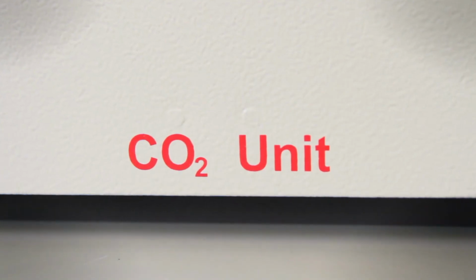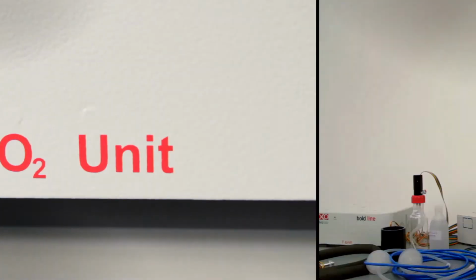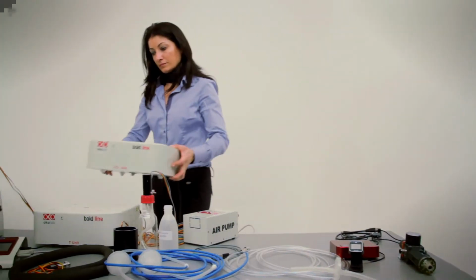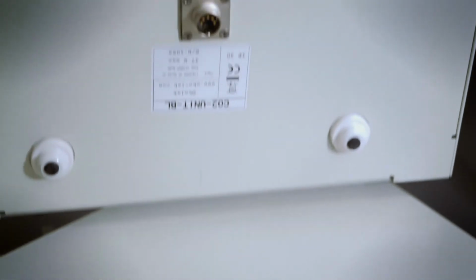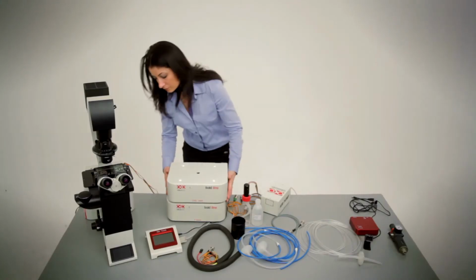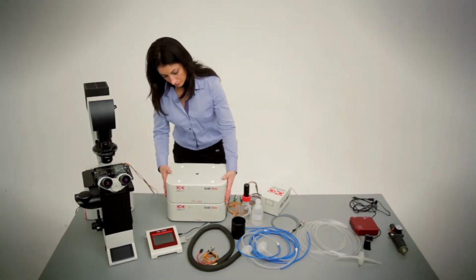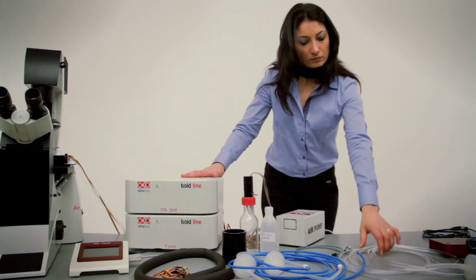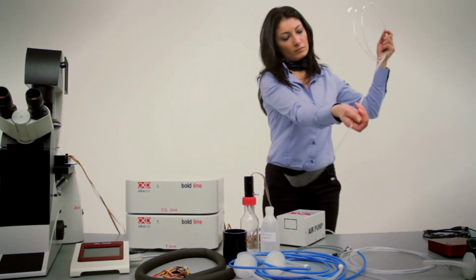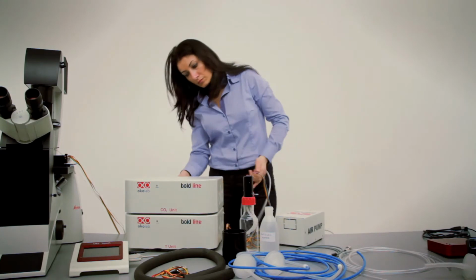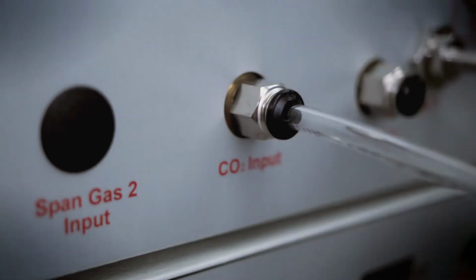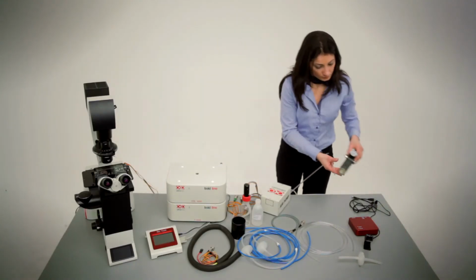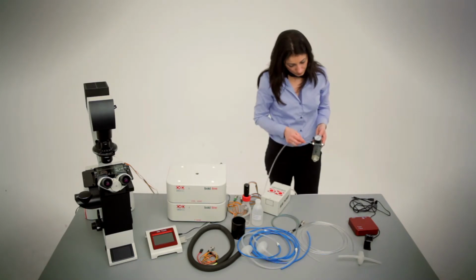Step 2. CO2 unit. Connect the gas controller to the temperature controller through the cableless connector. The positioning order of the controllers is not relevant. Connect one of the two transparent silicon tubes to the CO2 input push-in connector. The other end of the tube should be connected to the pressure gauge supplied with the controller.